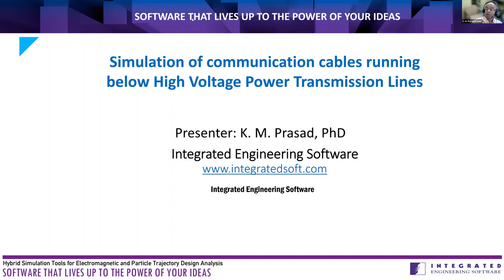So what is allowable? Basically these communication cables, they are dielectric materials, and they should not be exposed to very high fields due to these power transmission lines. So all these things can be simulated before erecting. You can simulate and decide what should be the gap between the communication cables and the power cables. You can decide it.